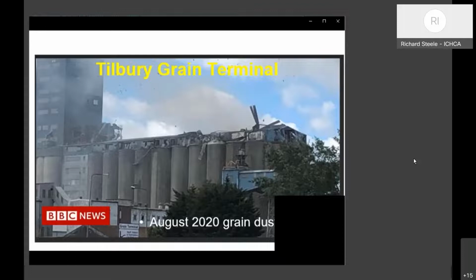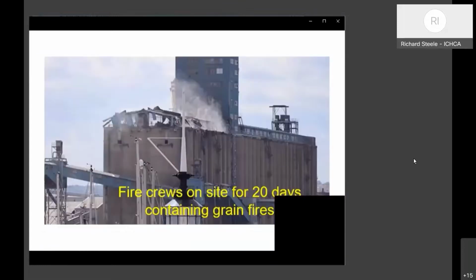And the thing that I never liked about Tilbury Grain Terminal, because I spent a lot of time at Tilbury Grain Terminal over the years, look where the offices and the control room are, right in the middle of the silo block. Now, if this explosion had been much worse, it could have wiped out everybody that could have done anything about controlling the incident. So there's a lesson there. Don't put your control rooms and offices in the middle of silo complexes. Fortunately, it wasn't as bad as it might have been.